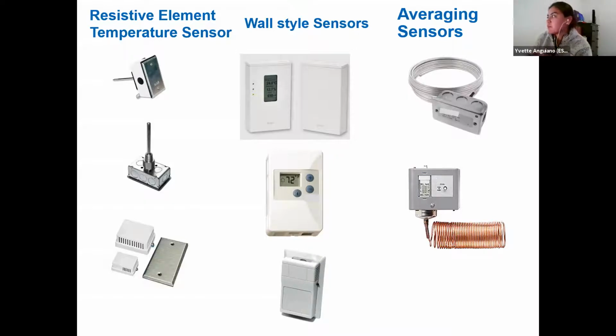And then lastly, we've got averaging sensors. Those would typically be used in a space where there's low airflow or stratification, in a position such as in front of a coil. You also have the averaging sensor, which would be attached to a safety device such as a freeze-stat, so that when it senses a very low temperature, like at the bottom of the duct, because typically the cold air falls, it would initiate that safety sequence to avoid freezing your coil.